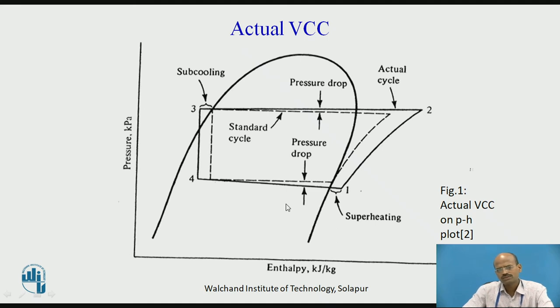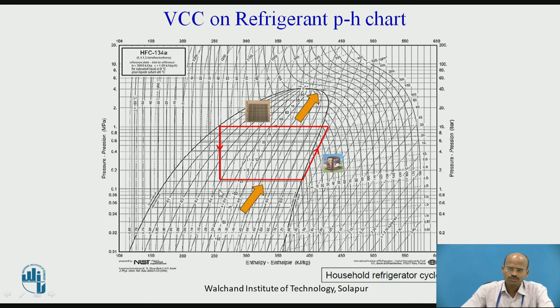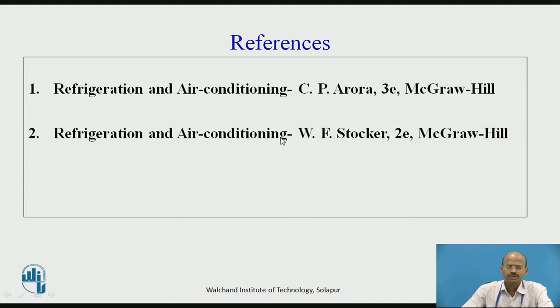This is the actual VCC, and for comparison purposes you can consider the schematic diagram of theoretical VCC. I can represent the VCC on a p-h chart: 1 to 2 is isentropic compression, 2 to 3 is isobaric condensation, 3 to 4 is isenthalpic expansion, and 4 to 1 is the refrigerating effect. To obtain the actual VCC, measure the actual pressures and temperatures, locate the points at inlet to compressor, outlet of compressor, outlet of condenser, and inlet to evaporator, then simply join those points. For further study, you can refer to Refrigeration and Air Conditioning by C. P. Arora and W. F. Stocker. Thank you.